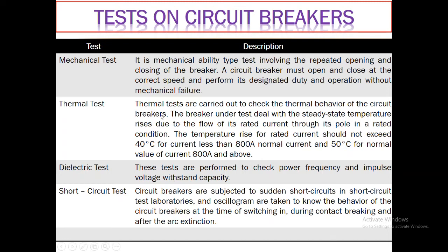The mechanical test is usually conducted on the circuit breaker to decide its ability to sustain mechanical forces. During the mechanical test, the testing engineer is expected to analyze the opening and closing time and the opening and closing speed of the circuit breaker contacts.